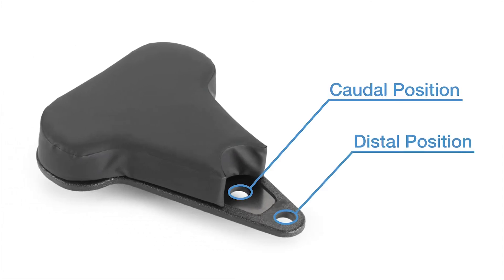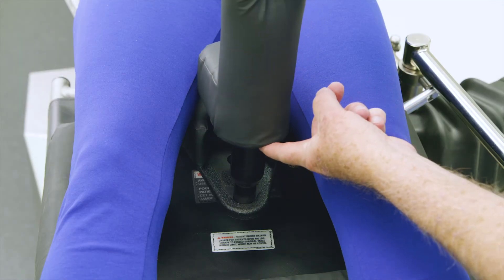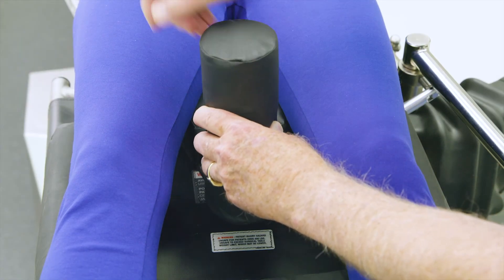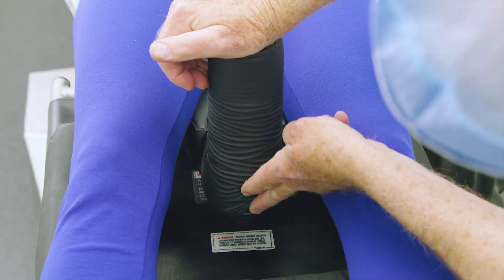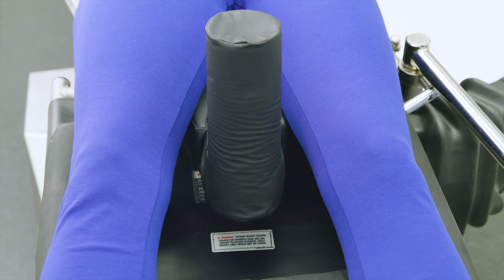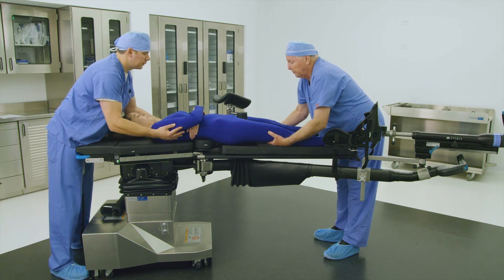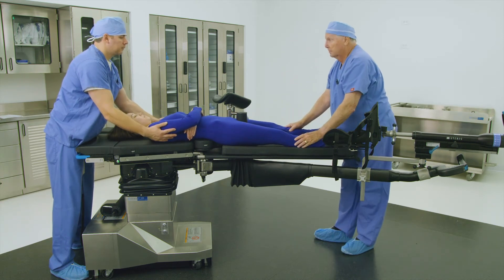There are two positions in the sacral rest to facilitate positioning requirements for a range of patients and to improve imaging area with unobstructed views. Most patients require the post inserted in the distal position; taller patients typically require the post inserted in the caudal position. Place the desired perineal post and pad into the appropriate hole on the sacral rest. Ensure the post is fully seated — failure to ensure correct placement could result in patient injury during active traction. Finally, shift the patient snug against the perineal post, ensuring there is no space between the patient's perineum and the perineal post.